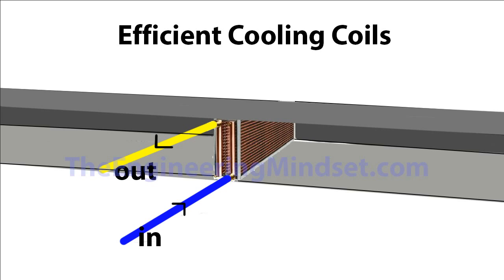If you do find one on your site, please first check with your manufacturer to make sure it has been fully designed for that operation. Another check is that the inlet for the chilled water should always be on the right-hand side — the furthest part away from the direction of airflow. If the inlet is on the face closest to the direction of airflow, then the coil has been installed incorrectly also — unless the manufacturer has specifically designed it for that purpose, so please check with them.